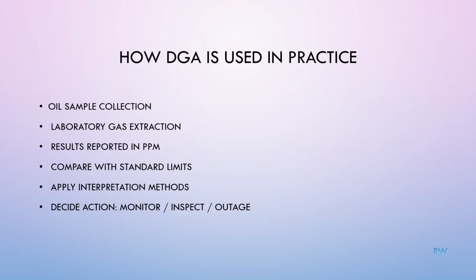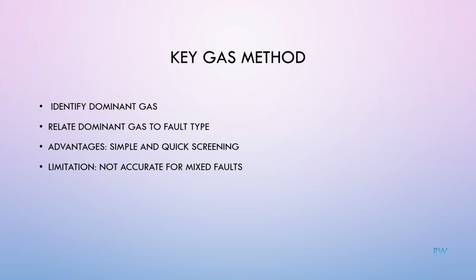In practice, oil is sampled carefully from the transformer. The laboratory extracts dissolved gases using gas chromatography. Results are reported in parts per million, or ppm. These values are compared with standard limits. Interpretation methods are applied. Based on results, a decision is made to monitor, inspect, or take the transformer out of service. The key gas method identifies the dominant gas present. The dominant gas is then associated with a specific fault type. This method is simple and useful for initial screening. However, it may not be accurate in complex or mixed fault situations.